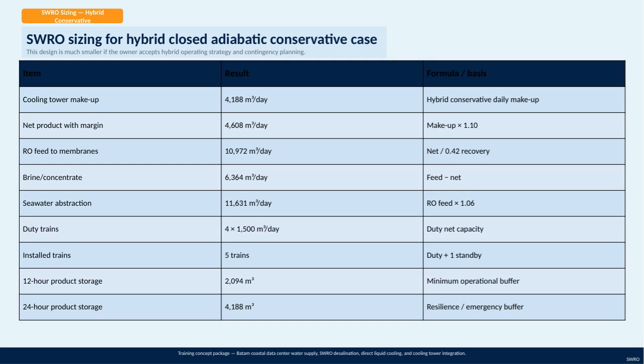Here we have the SWRO sizing for a hybrid closed adiabatic conservative approach. This design is notably smaller, provided the owner agrees to a hybrid operating strategy combined with contingency planning. Taking a closer look at the table, the cooling tower makeup water requirement is 4,188 cubic meters per day under this hybrid conservative daily makeup scenario. To ensure a safety margin, the net product output is calculated at 4,608 cubic meters per day, which is 10% higher than the makeup volume.